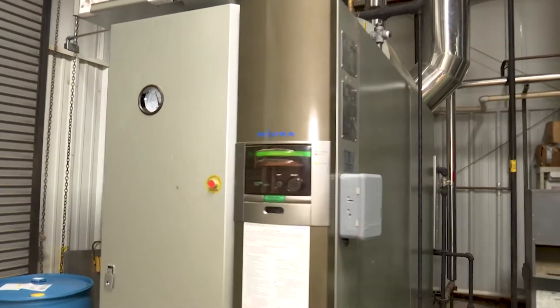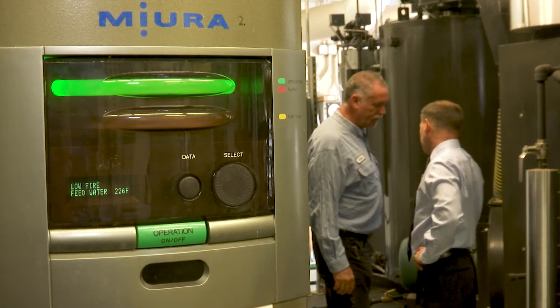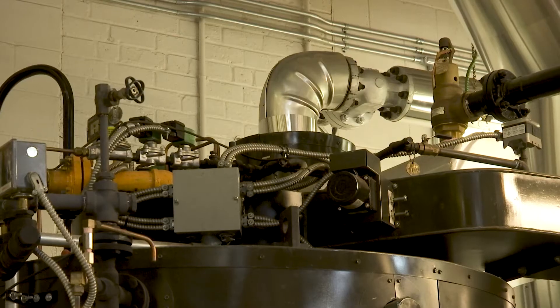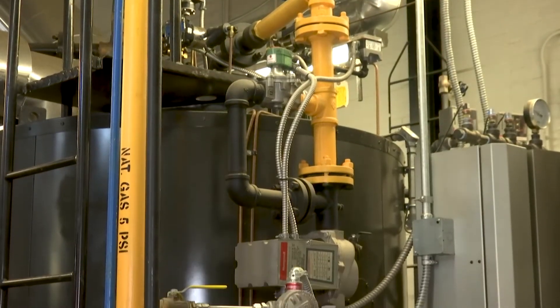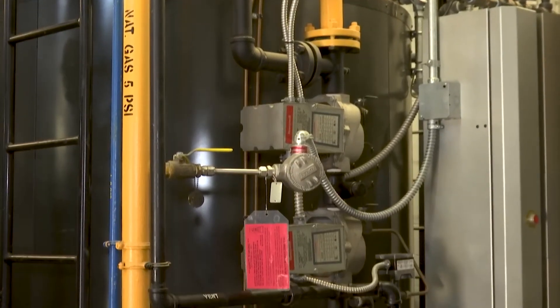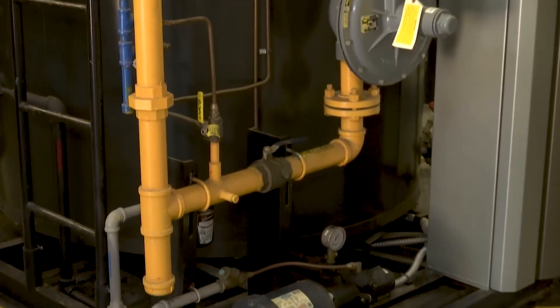EX series are available in 100 HP and in 50 HP increments up to 300 HP models. Their unique floating header design concept allows for even thermal expansion of the tubes, therefore reducing stress points within the boiler. The leaky tube problems associated with fire tube and bent water tube designs have been eliminated.